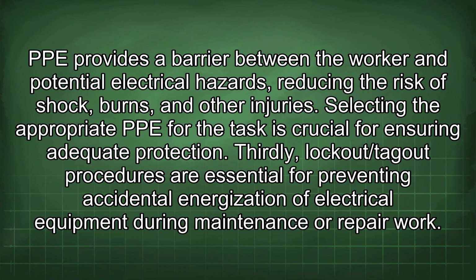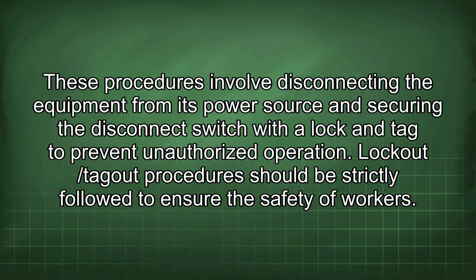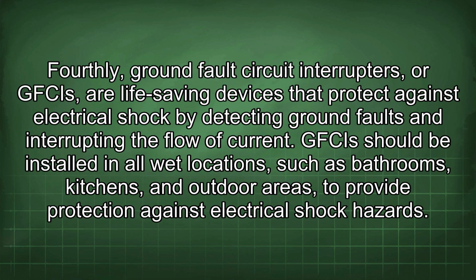Thirdly, lockout/tagout procedures are essential for preventing accidental energization of electrical equipment during maintenance or repair work. These procedures involve disconnecting the equipment from its power source and securing the disconnect switch with a lock and tag to prevent unauthorized operation. Lockout/tagout procedures should be strictly followed to ensure the safety of workers. Fourthly, ground fault circuit interrupters, or GFCIs, are life-saving devices that protect against electrical shock by detecting ground faults and interrupting the flow of current.